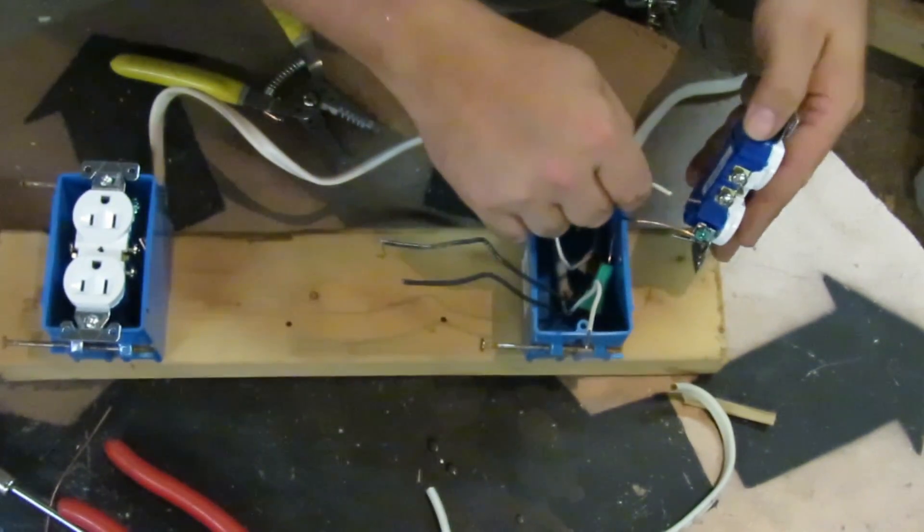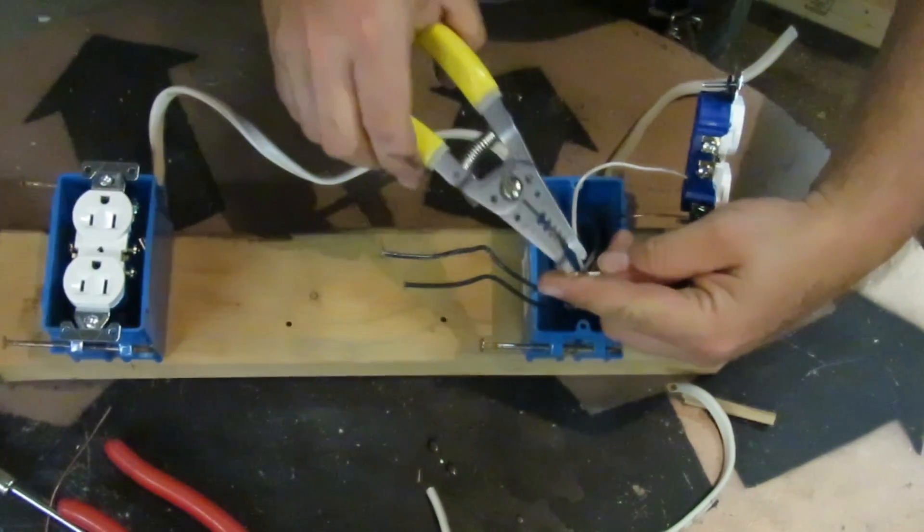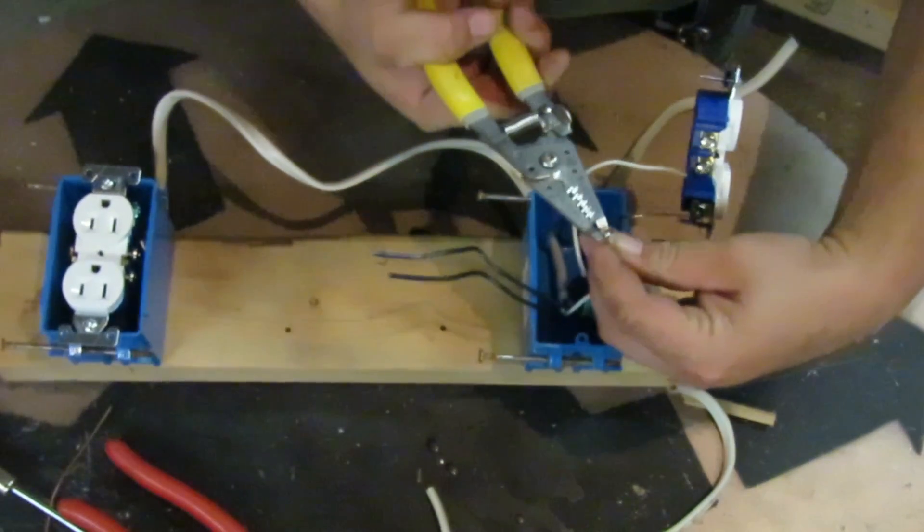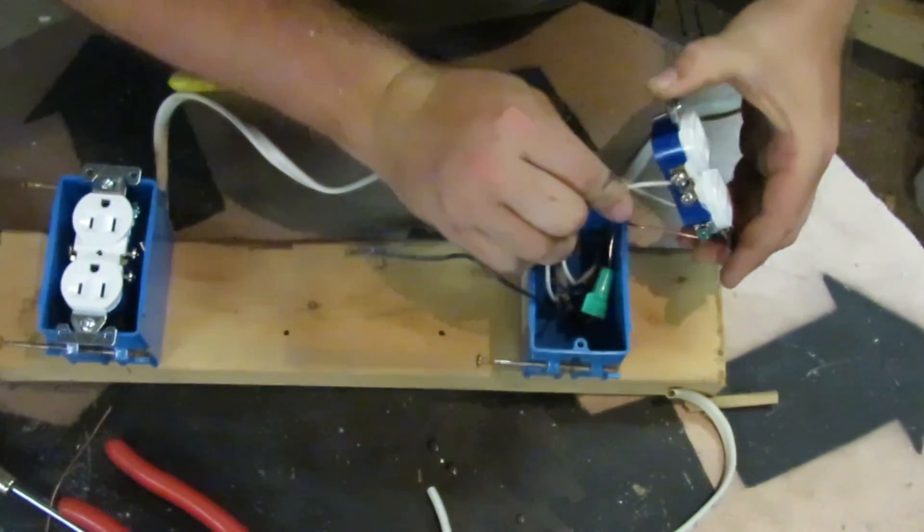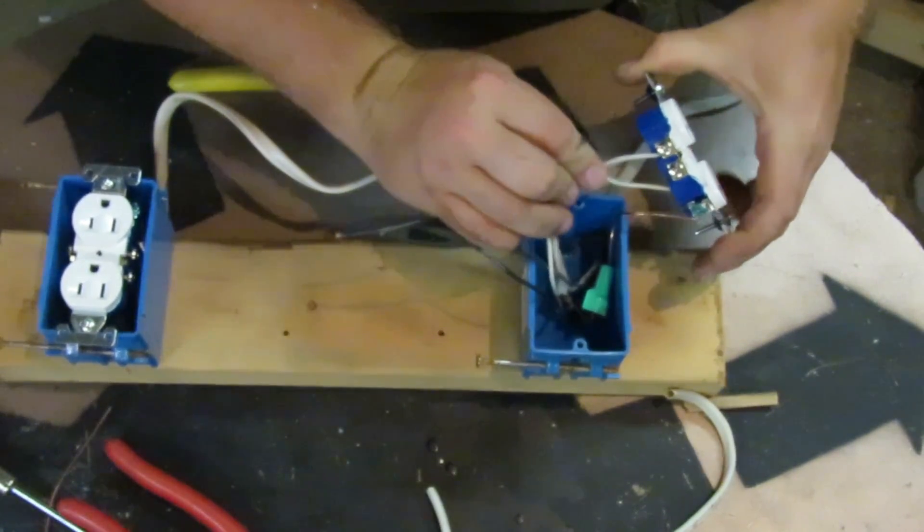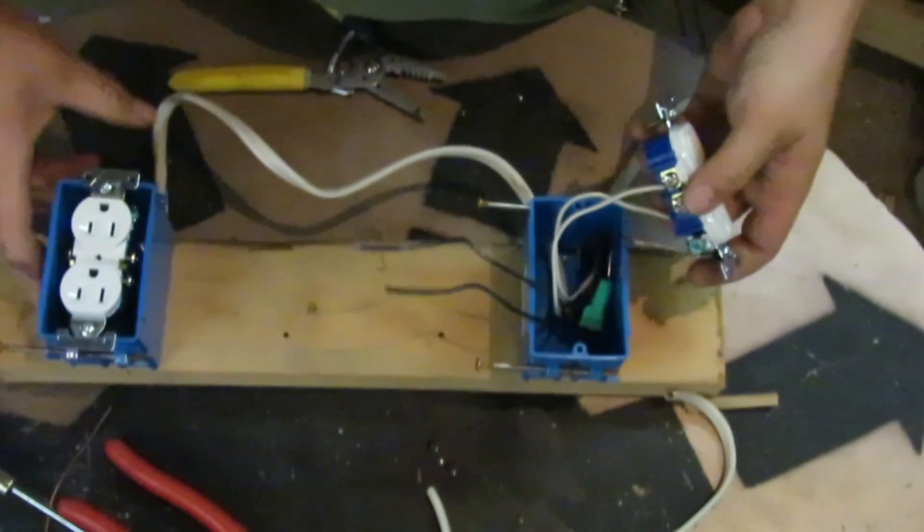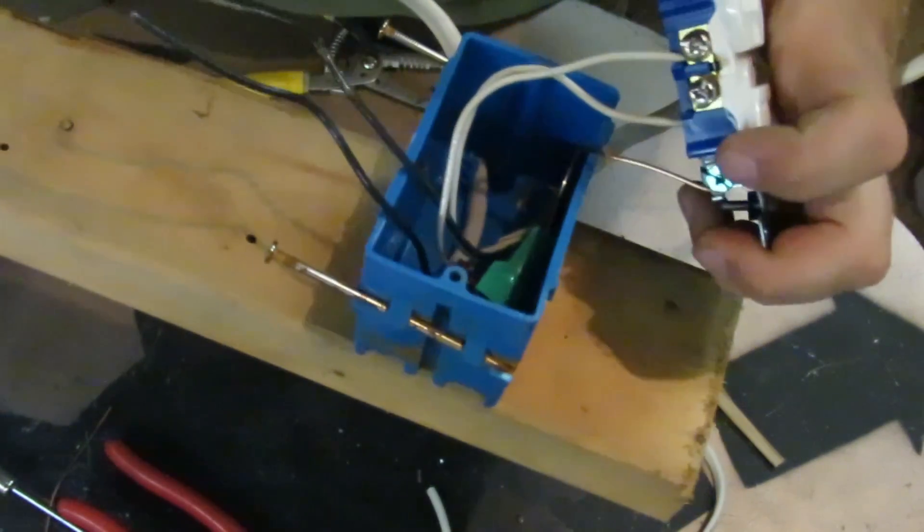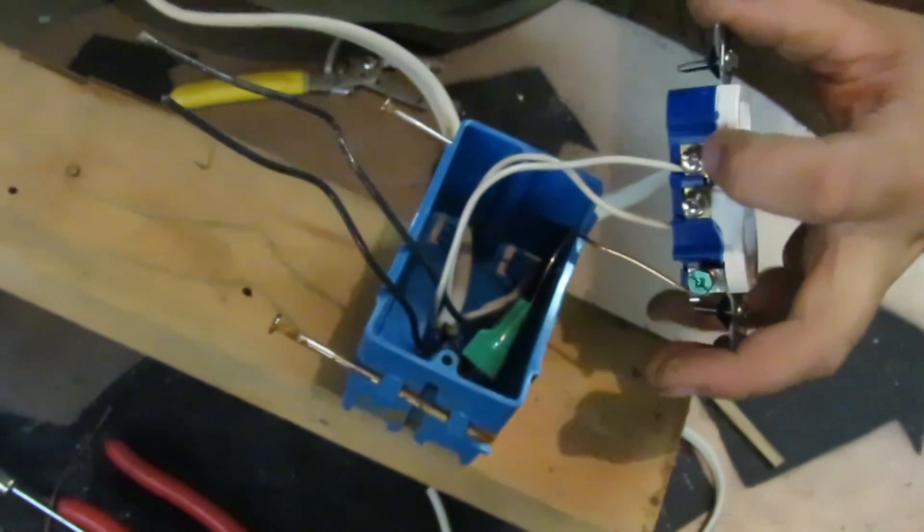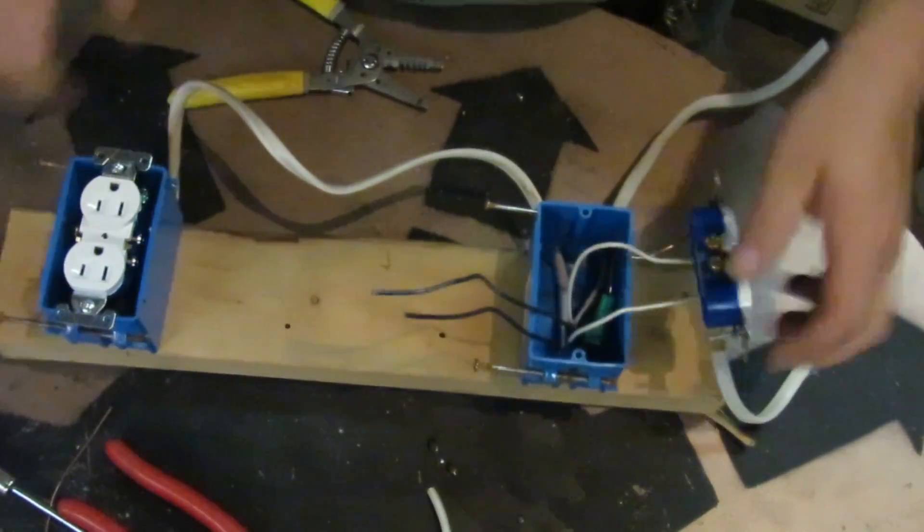Now you don't have to push them in the back. You can actually hook them around the screws if you want. It doesn't really matter, as long as they're on the same side. As long as your neutral wires are under the silver screws, it'll work just fine. You see the bottom one is pushed in and the top one's around the screw. And that'll work just fine.